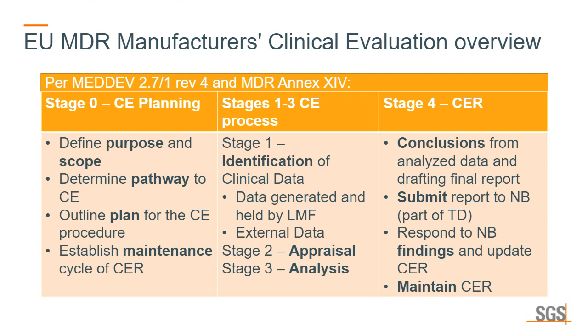I mean, there can be many failure modes at this stage, but the one thing that we often see, especially for novel technologies, is that some of these scientific literature articles may have a conclusion which clearly explains that the study was inconclusive, or requires additional follow-up in the future because the technology is rapidly evolving, or we don't know the long-term physiological effect of the device. And that level of uncertainty is skipped from being represented in the final report.